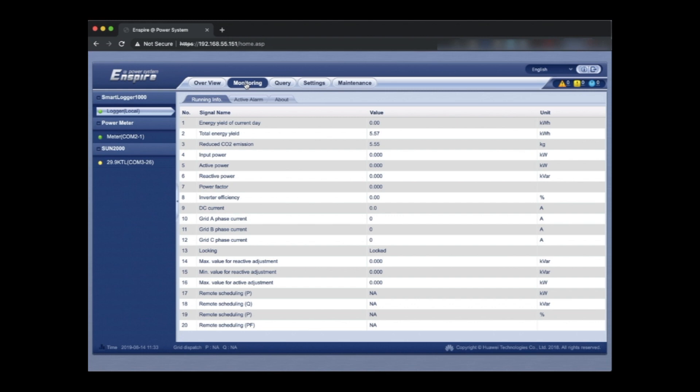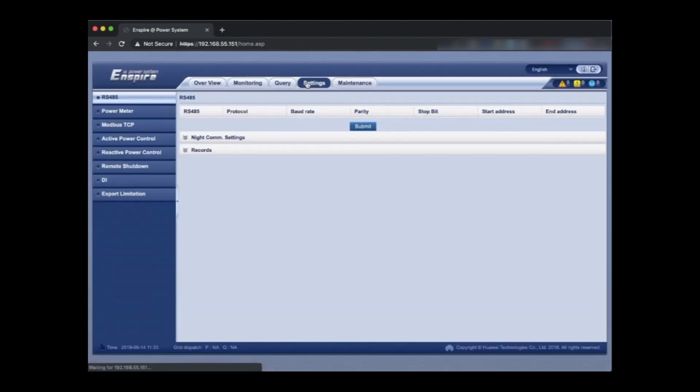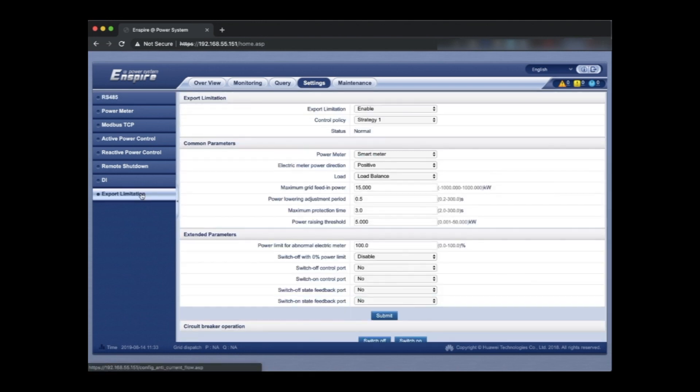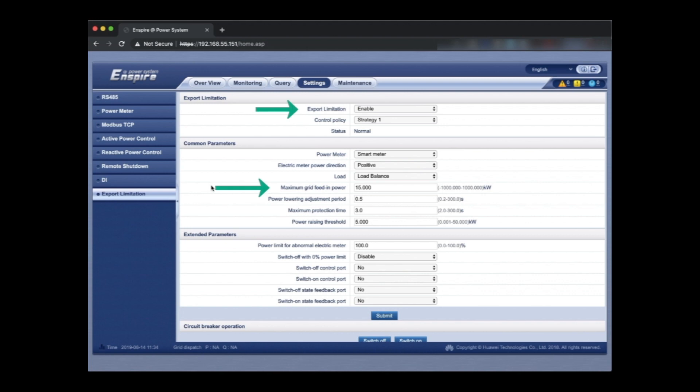This unit is currently not generating so we're not seeing any active power. So next we're going to look at how to export limit. This is often a requirement by DNSPs or utilities when installing a system on a commercial installation. So we select export limitation. This is super easy. We really just need to set what the kilowatt maximum grid feed in power is. It's defaults to 15 kilowatts. You can adjust that up to the maximum power of the inverter and right down to zero. So we're just going to change it in this case to 20 kilowatts which is what we're allowed to do.